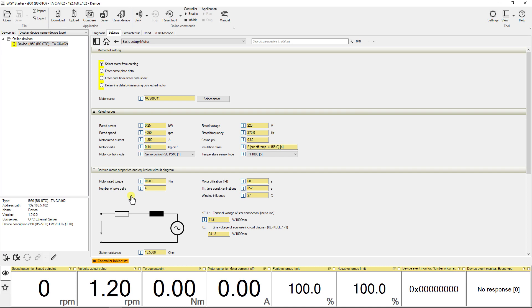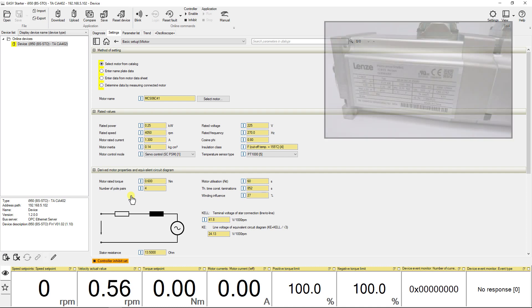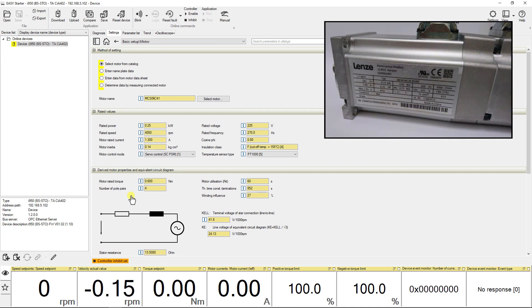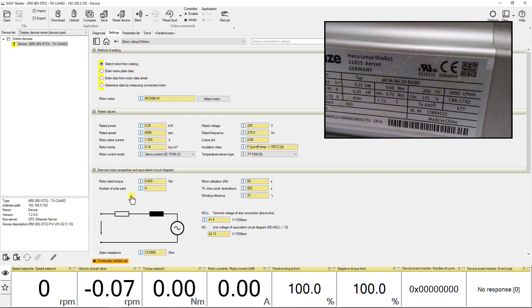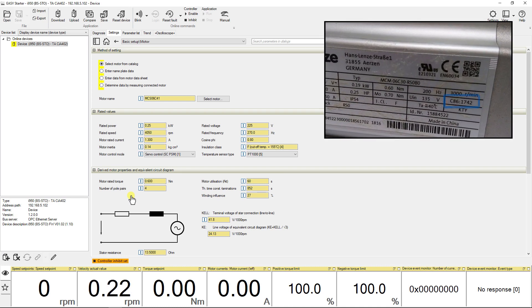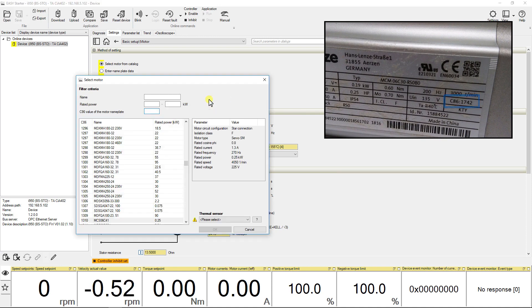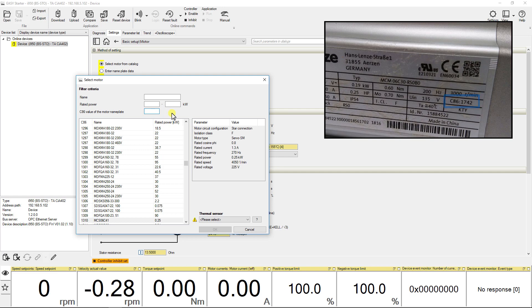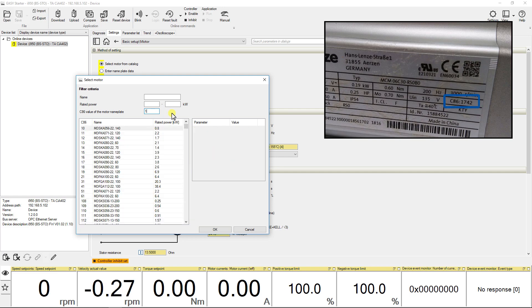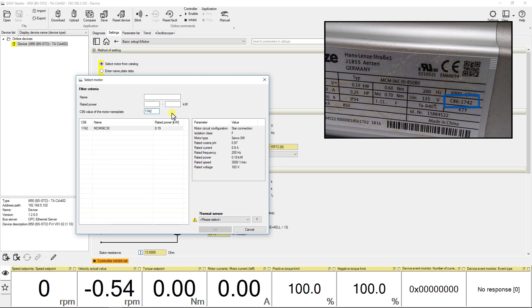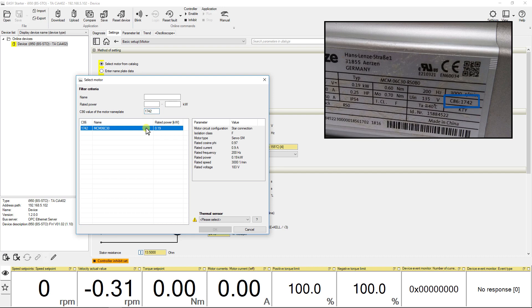Every Lenze motor comes with C86 code marked in its nameplate. Go to the option select motor and click on it. Put the C86 value of motor nameplate. Here the code is 1742. This will set all motor data in the drive.